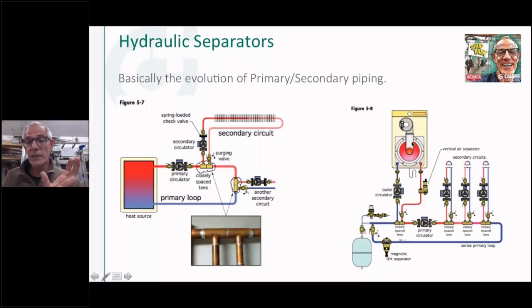And this is where it really helped us a lot. We said, okay, let's take the boiler out of this loop now, like we have over here, call that a cast iron boiler, low pressure drop. We can flow through that pretty easily. This boiler needs to have a circulator dedicated to it to overcome that pressure drop. Well, by tying it into the loop with these closely spaced T's, now we can size that appropriately.